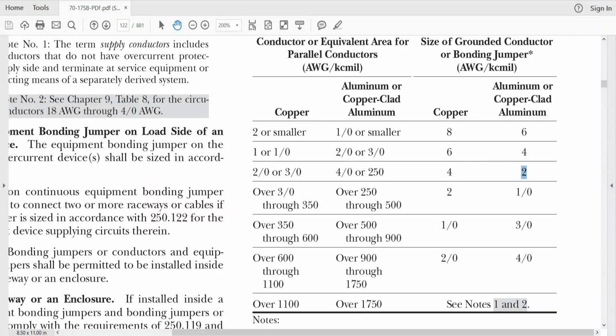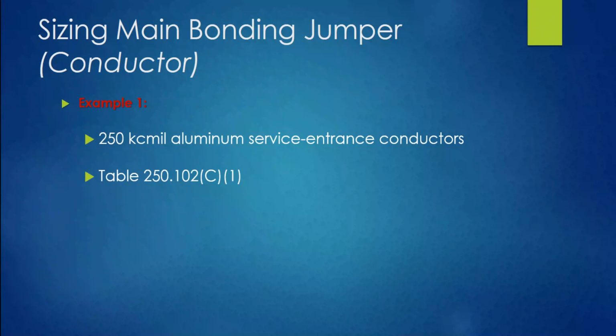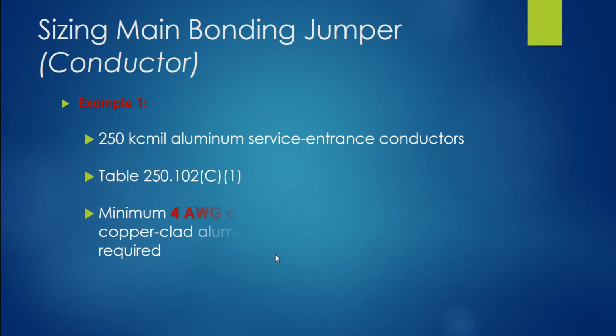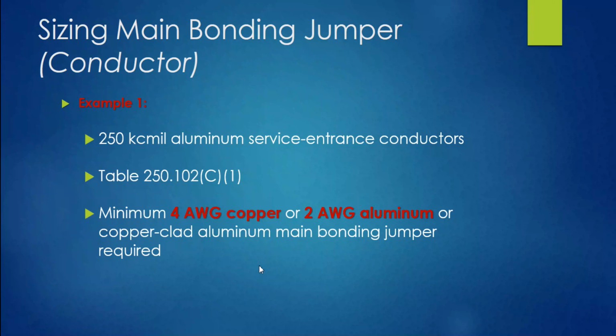All right, now we're not going to get into the other part of the notes just yet, but what I want to do is come back to the presentation, and we'll see if we sized it right. And there you go. So the size here would be a 4 copper or a 2 aluminum, whatever the choice may be. Yes, and you can also use copper-clad aluminum. Don't see a lot of it out there, and my primary conductor of choice would be copper, but there's absolutely nothing wrong with aluminum. And yes, you can get bonding jumpers in aluminum. Obviously we sell plenty of aluminum wire. You can use the aluminum wire as a bonding jumper.